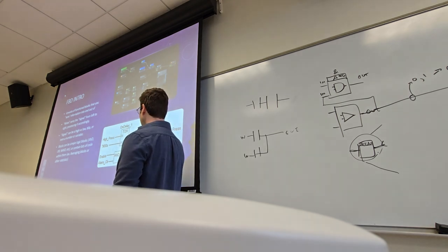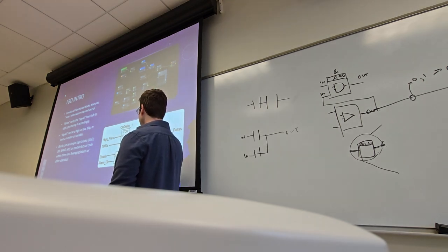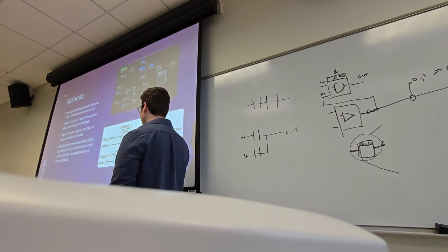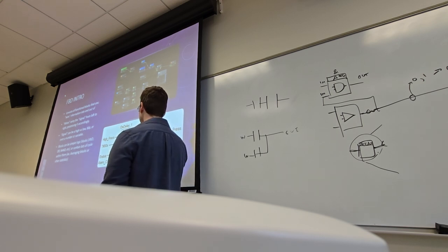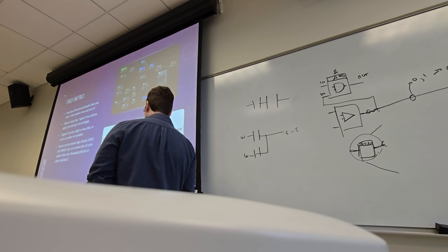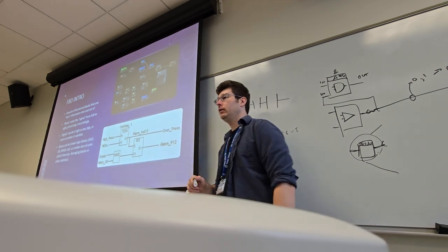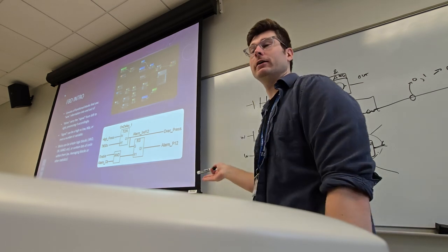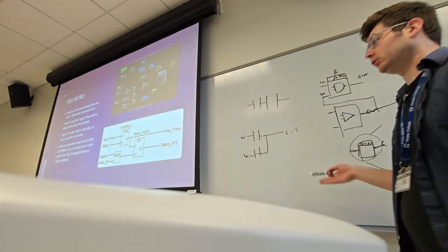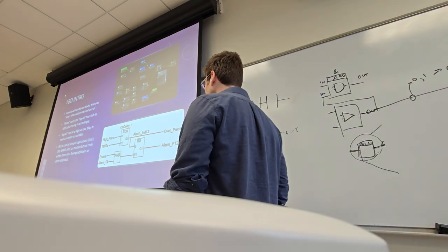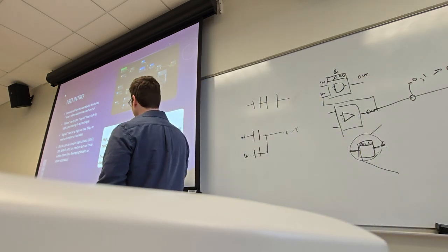Okay, so here we have the set bit, where if this goes high, then this will output high, and it will always output high forevermore. It latches on unless we click on to its reset pin. If this goes high, then this unlatches back down to low, and that's a useful thing to have as well, depending on the logic that you're trying to do in your program, storing the state of a bit or clearing an alarm, whatever is useful.